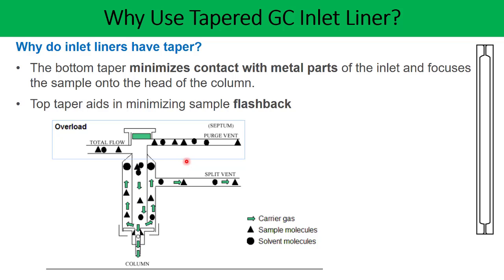Because of flashback, you will have irreproducible results from injection to injection. There could be a chance of ghost peaks or cross contamination. So flashback is not good for gas chromatography. The top taper can certainly minimize this flashback because it avoids the transfer of the solvent or vaporized sample towards the inlet gas line, carrier gas line, or the septum purge vent.